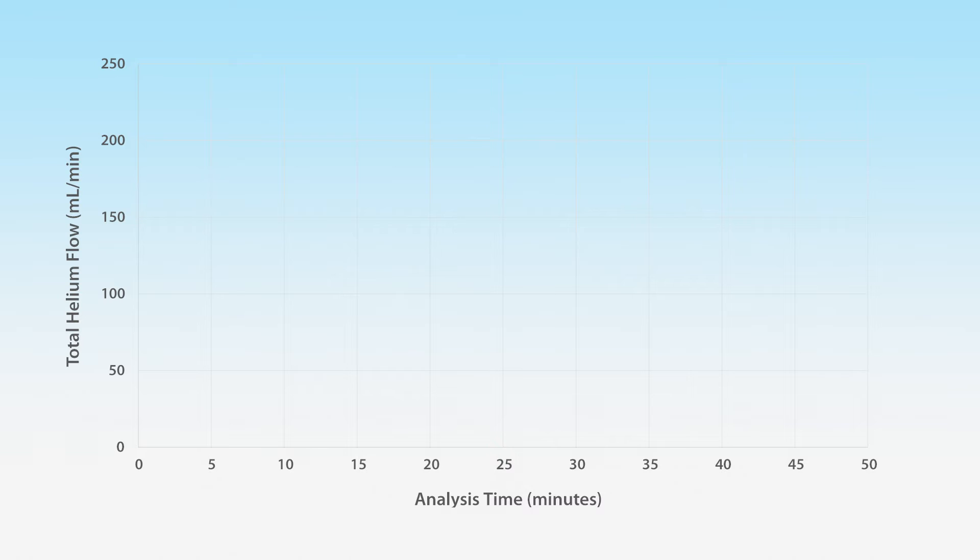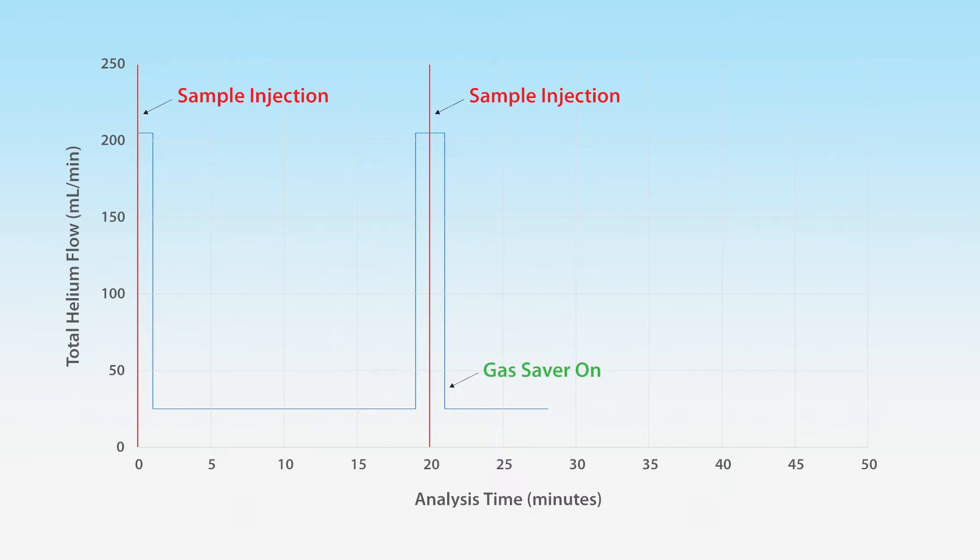Gas Saver Mode activates one minute after sample injection, which reduces our split flow to our set rate of 20 milliliters per minute. Our column flow and septum purge are unchanged, resulting in a total helium flow of 25 milliliters per minute.